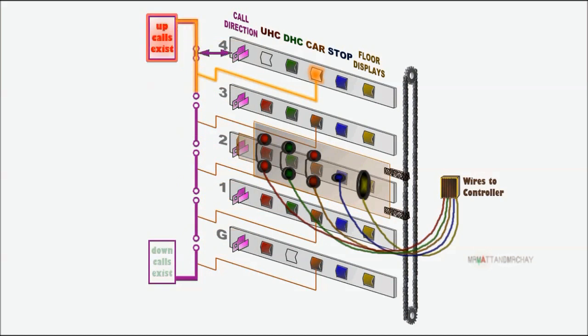Here, the fourth floor car call can now reach only the up request relay. At the third floor, the lift is not here, so the line joins together. The carriage is at the second floor, so this breaks the line. Now you can see that the car call that's above the lift can only reach the up request and cannot get to the down request. Now, when a lift gets a request, it will always commit to this direction until it reaches the furthest call.